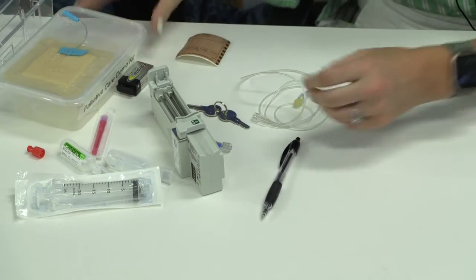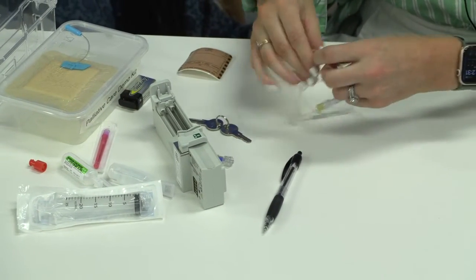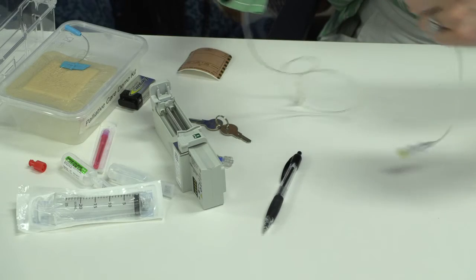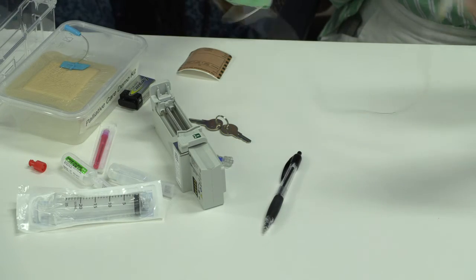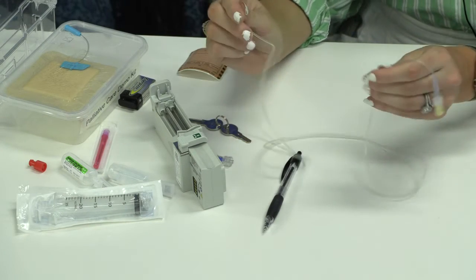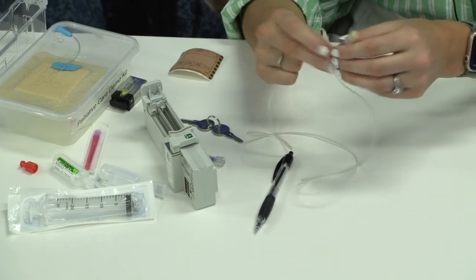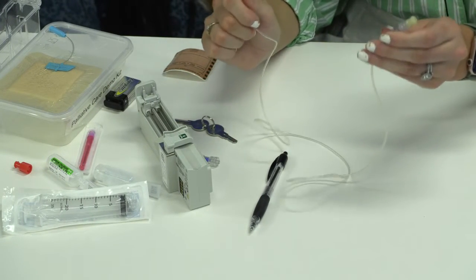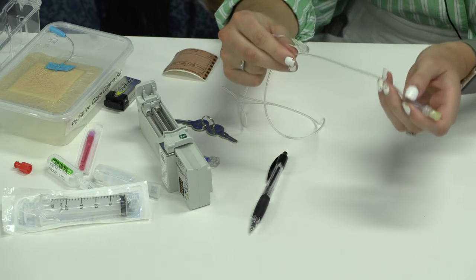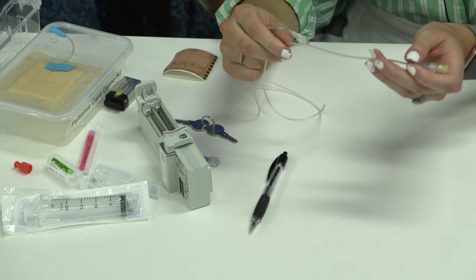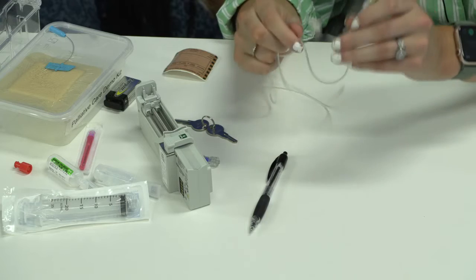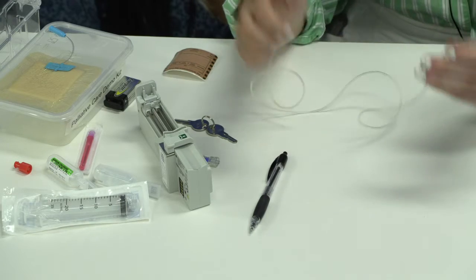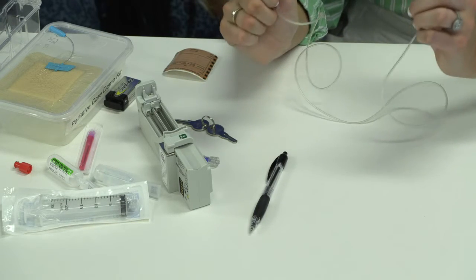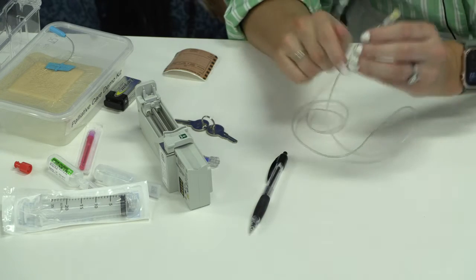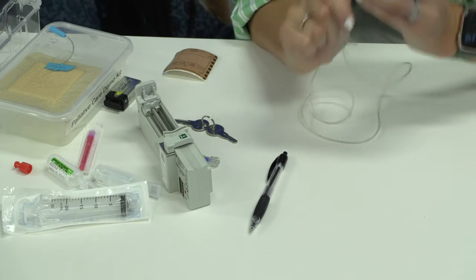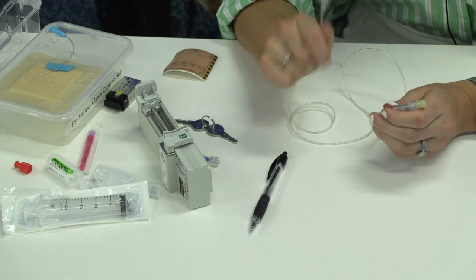We need an infusion extension set. So these are what we use. So these are 100 centimetre tubes, and they hold 0.8 mil of liquid. So the machines are calibrated to have no more than 1.2 mils primed through the line. So we need to ensure that when you order your lines, that the lines are compatible and no more volume than 1.2 mil over the entire line.